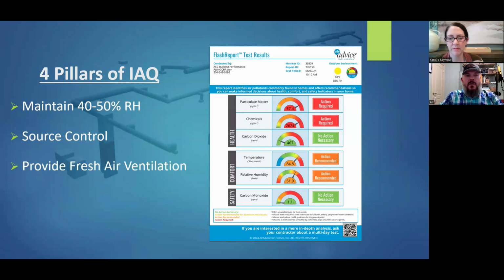Fresh air ventilation. We must have a controlled means of fresh air ventilation. A house does not need to breathe. We need to breathe. That's a whole other presentation in itself. Check out Dr. Allison Bale's book, A House Needs to Breathe, or Does It? Excuse me. Superior filtration. A MERV 16 if possible. In my opinion, a MERV 13 minimum. However, the system must be designed for these. You cannot simply throw a MERV 13 or a MERV 16 filter at a system that was never designed for it. You will cause more problems than you're solving.